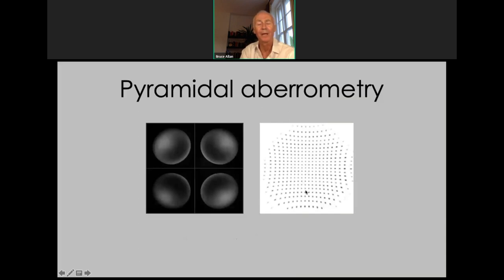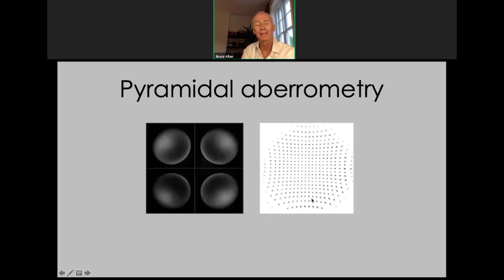This is a step forward from the Hartmann-Shack aberrometers used with other platforms, and the key difference is in avoiding problems with spot crossover. With Hartmann-Shack aberrometry, emergent light is sampled over the pupil and deviation from the expected locus is used to calculate wavefront information. With pyramidal aberrometry, a pyramidal element splits emergent light into four images of the pupil, and differences between these four images are used to derive wavefront information. This is important in therapeutic treatments because with Hartmann-Shack systems on very irregular corneas, spot crossover occurs — neighbouring sensors pick up light addressed to their neighbour's locus, making it impossible to measure beyond a certain stage of irregularity.